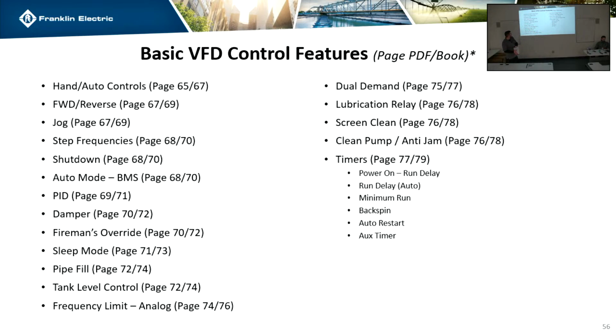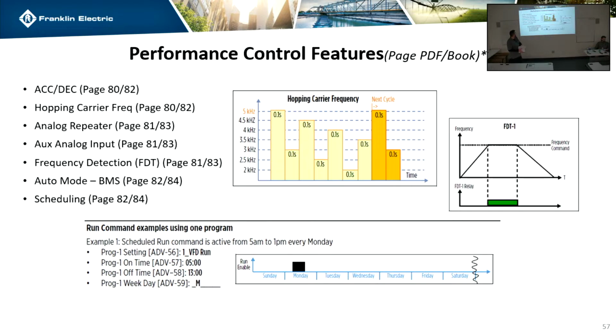Go to the next slide. So this is hopping carrier frequency. This is kind of another in the weeds one. If the customer is complaining that the motor itself is too loud when being operated with a VFD, I'm sure you guys have all heard the whine that can come. This is to get rid of that. It chops up the carrier frequency, and it goes between 3 and 5 and 2. It just bounces around, and it eliminates the noise for the most part. Like, dramatically improves it. So this will not change your functionality, your sleep mode, or anything like that. This is just a solution to a noisy motor.